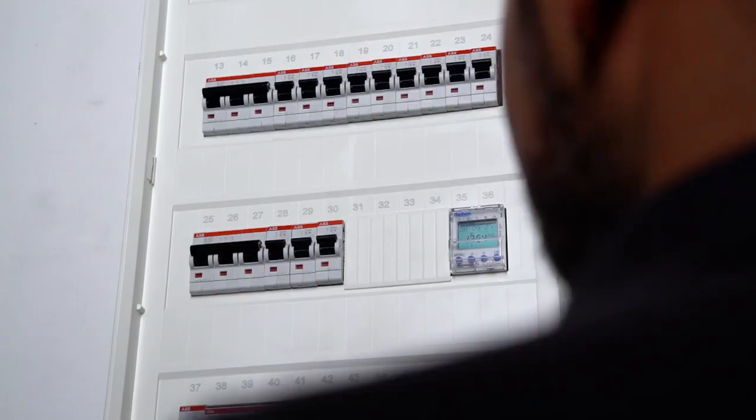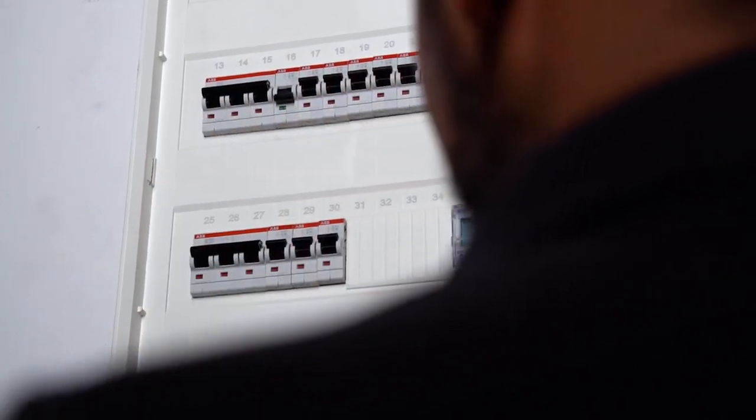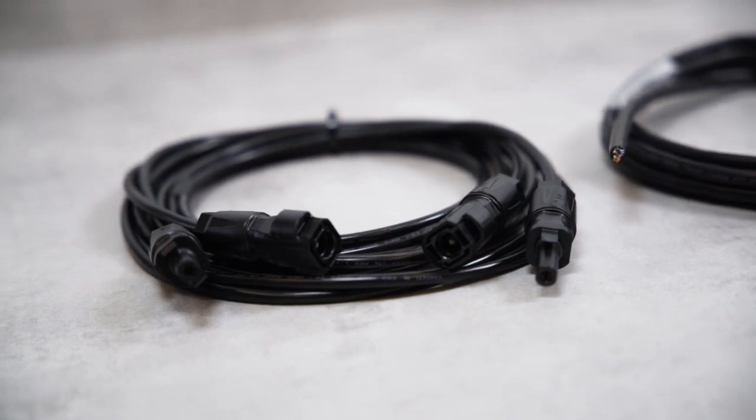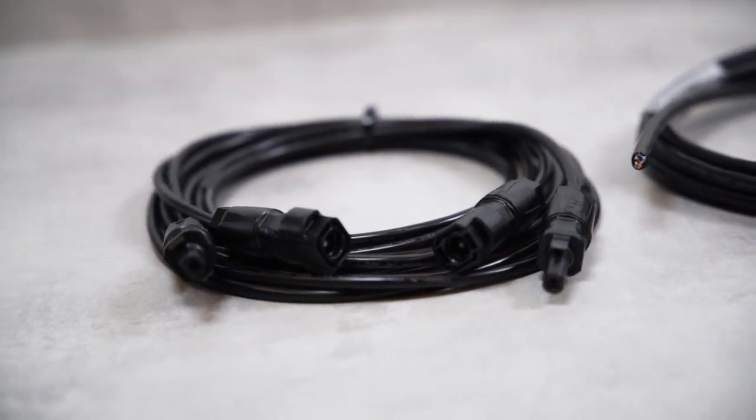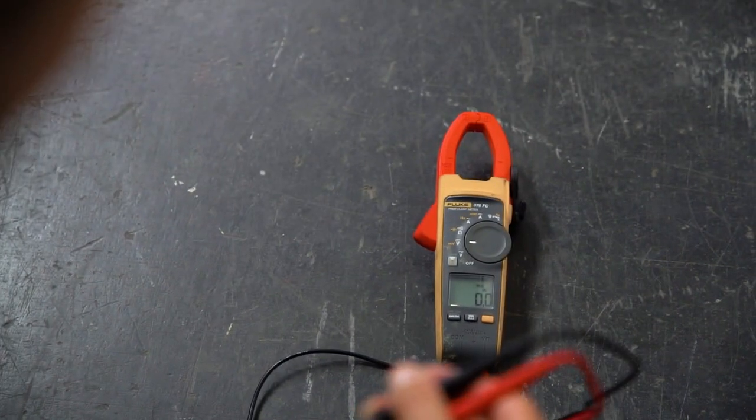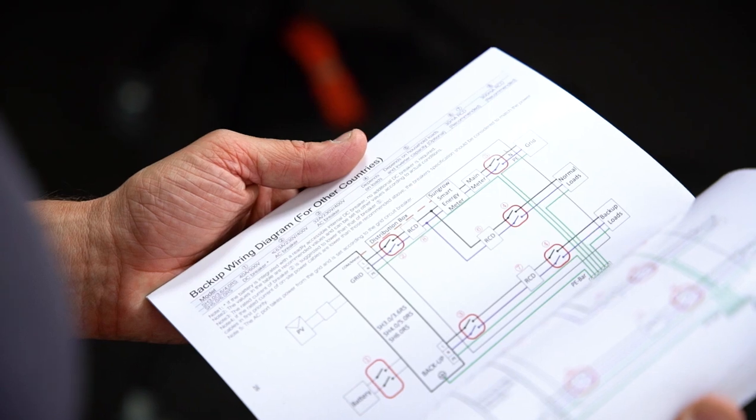Before the inverter can be connected, the AC home circuit breaker must be disconnected, the cables must be de-energized and in perfect condition. Before installation, make sure by measuring that the cables are really voltage free. You will find all cable requirements and wire sizes in our manual.